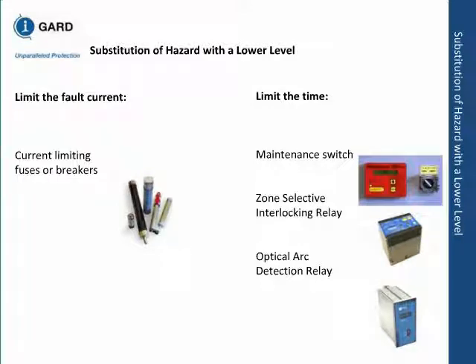You can have a zone selective interlocking relay, or the latest technology, optical arc detection, because when the flash happens, the first thing you see is light. Then you experience the sound and the pressure. So if you can take the first method that you can get, you're going to cut down the time that the flash persists.